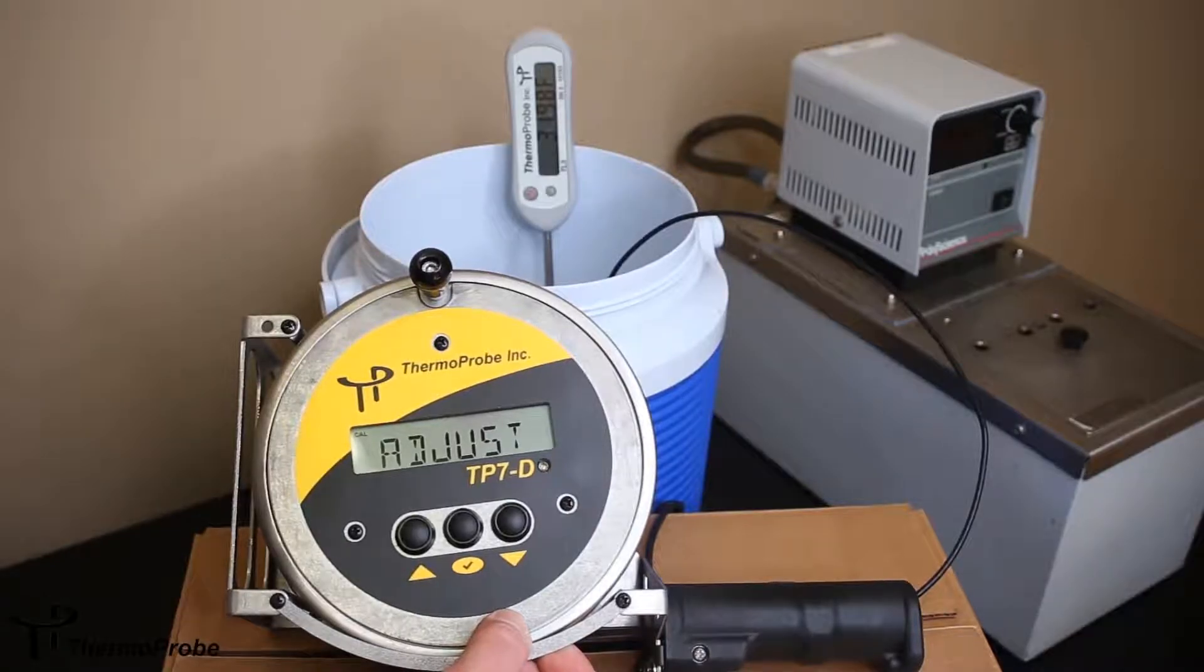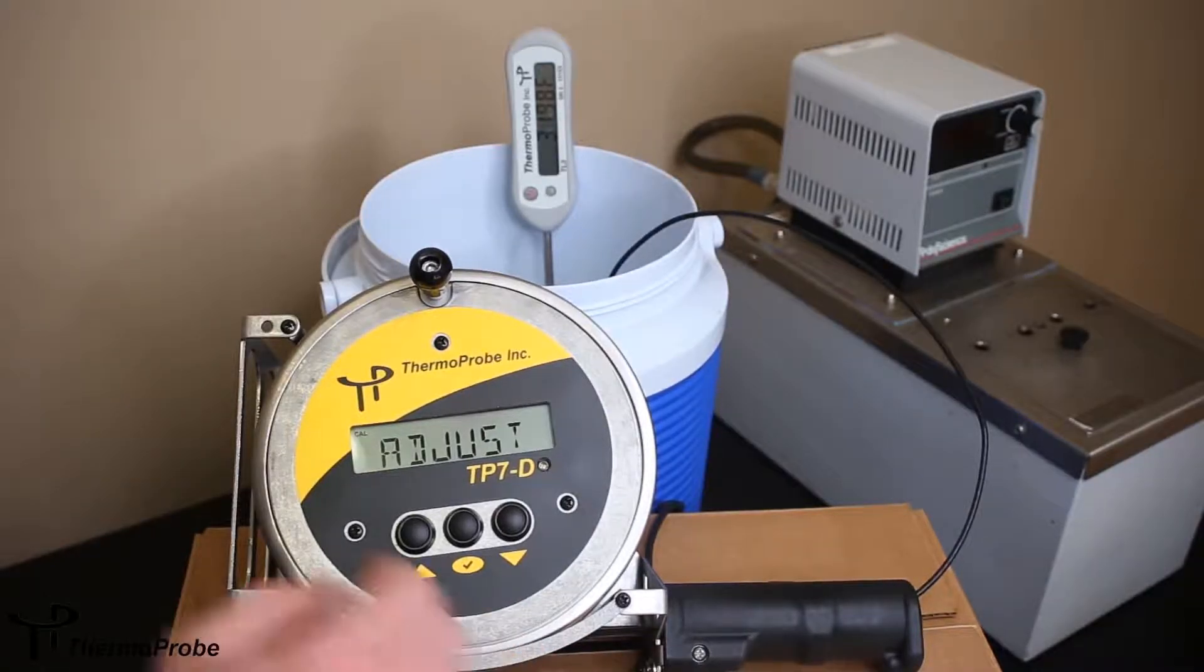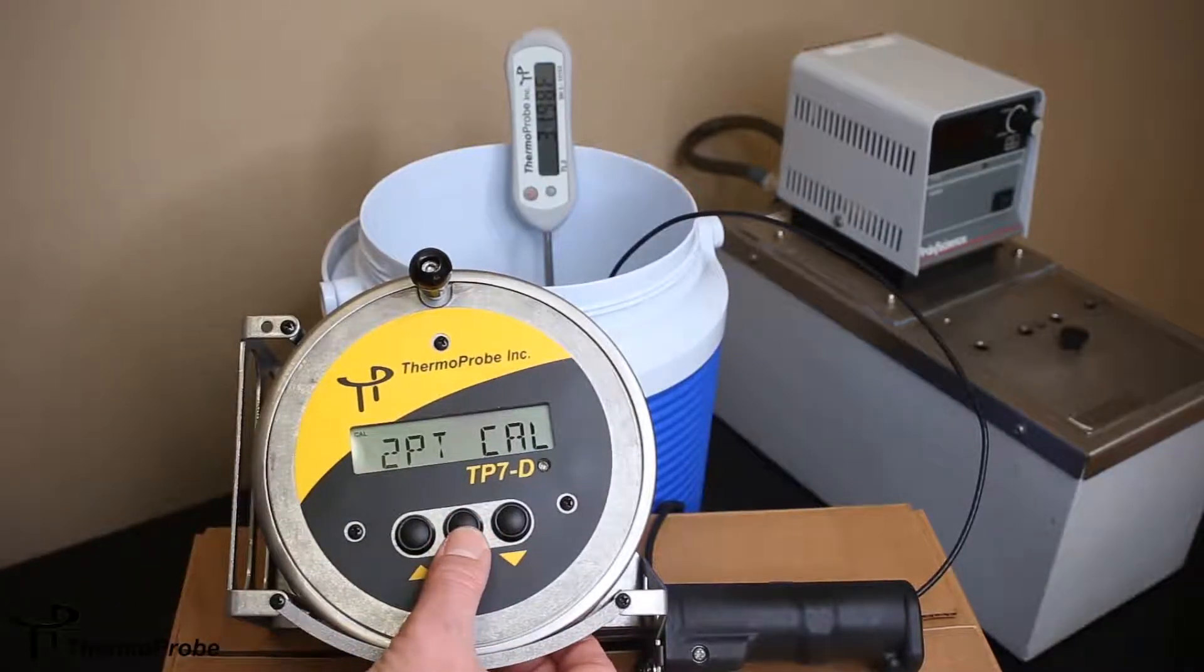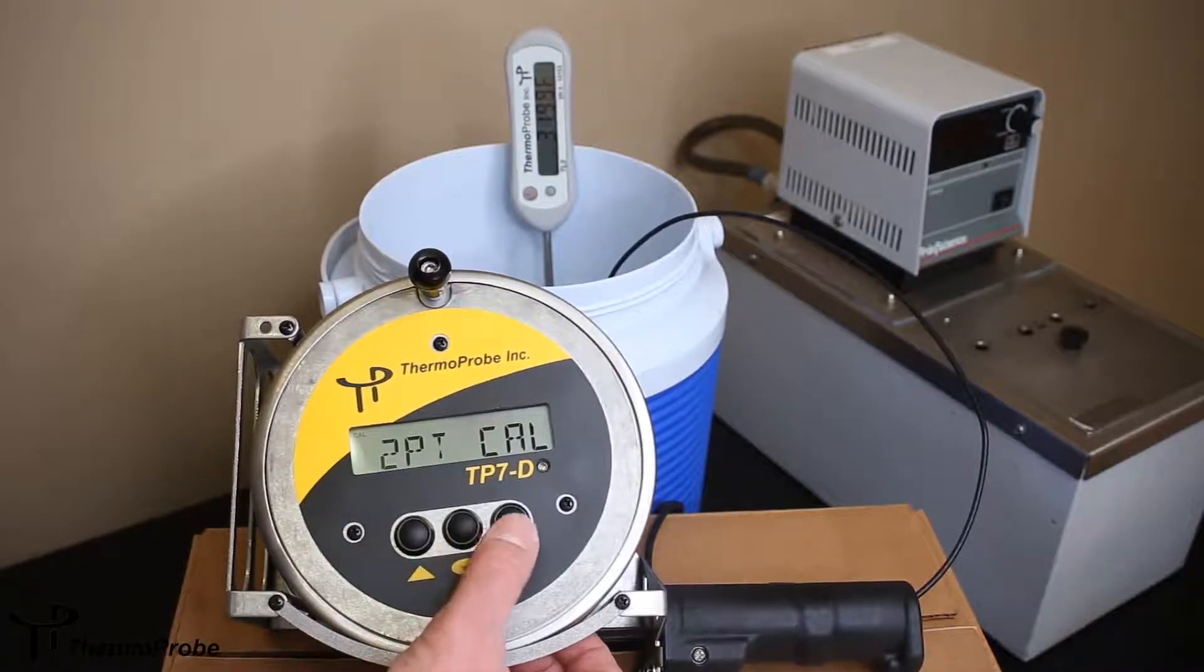Now I can decide if I want to make an adjustment, which I do. I also can see that I have a calibration icon. You can do a two-point, a three-point, or a four-point calibration. We're going to be doing a two-point.